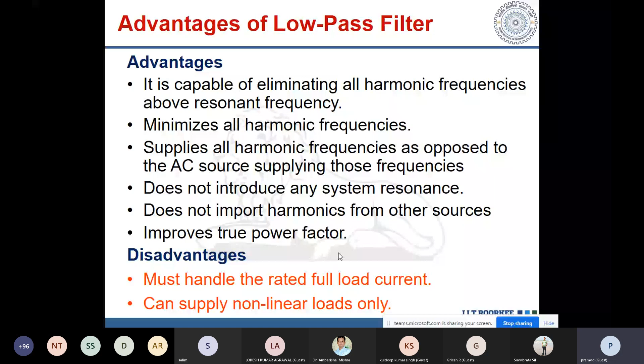Whenever you want to design a passive filter, as you can see, the shunt passive filter is the most commonly used filter. Now, while designing this filter, we can just see in brief. We are going to put this shunt passive filter across a particular nonlinear load, in parallel. If we know what harmonics are being injected by that load, we can put an appropriate passive filter to eliminate or absorb that harmonic. Let us say you want to eliminate 5th, 7th, 11th, and 13th. It means one filter for 5th, one for 7th, one for 11th, one for 13th. And each filter consists of L and C. How to calculate this L and C?